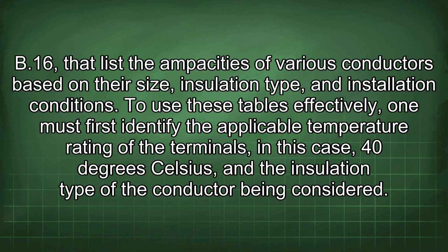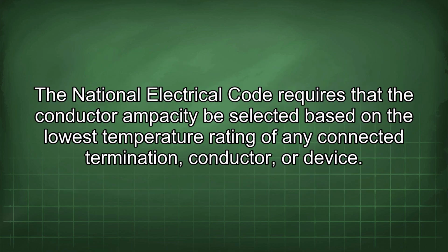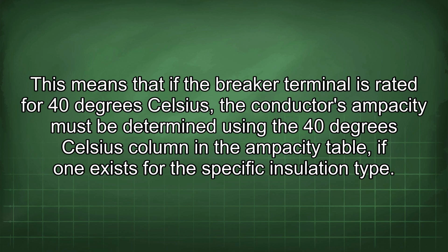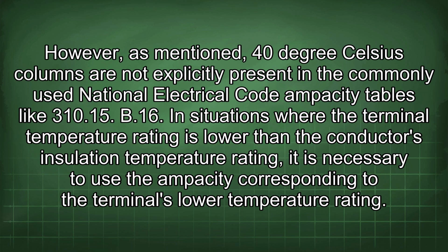To use these tables effectively, one must first identify the applicable temperature rating of the terminals, in this case 40 degrees Celsius, and the insulation type of the conductor being considered. The National Electrical Code requires that the conductor ampacity be selected based on the lowest temperature rating of any connected termination, conductor, or device. This means that if the breaker terminal is rated for 40 degrees Celsius, the conductor's ampacity must be determined using the 40 degrees Celsius column in the ampacity table, if one exists for the specific insulation type. However, as mentioned, 40 degrees Celsius columns are not explicitly present in the commonly used National Electrical Code ampacity tables like 310.15(B)(16).